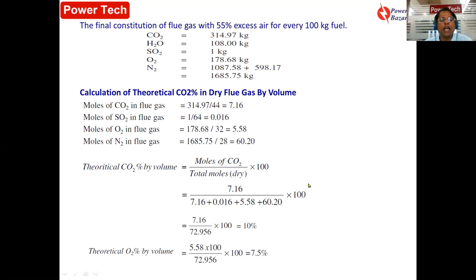Now let us understand what the energy conservation options in fuel oil firing are. There are four options. One is optimizing excess air and combustion. Excess air leads to stack loss. As I told you, it leads to dry flue gas loss. But if you supply less air, it will lead to incomplete combustion. That means you have to optimize the excess air to achieve good combustion efficiency. It should not be more, it should not be less.